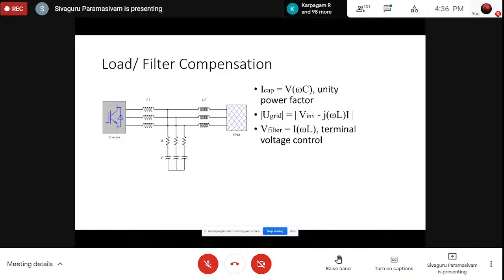Okay, this is one of the most important. You can see we have the inverters, we know the inverters, power electronics, but we cannot connect that to the grid. I told you about using the LCL filter. Sometimes even the C has an R because the R is a damping resistor here. Whenever we are charging the capacitors for the first time, it could take a huge inrush current, and we need to have some damping resistors for smoothly charging the capacitor. That's why you see an R here. And with this setup, we can have the grid get cleaner power with lesser harmonics and lesser turbulence. So that's why we have this control system also.